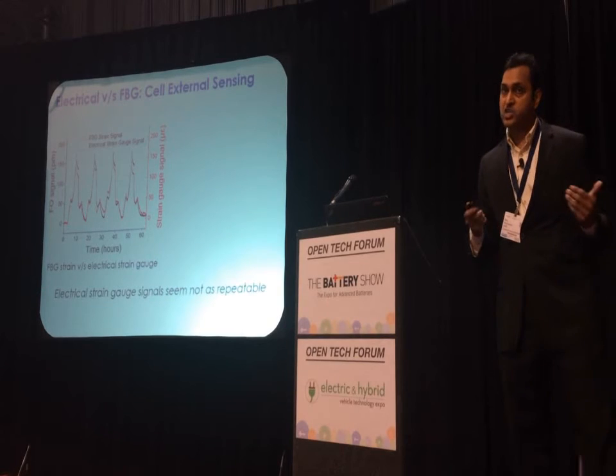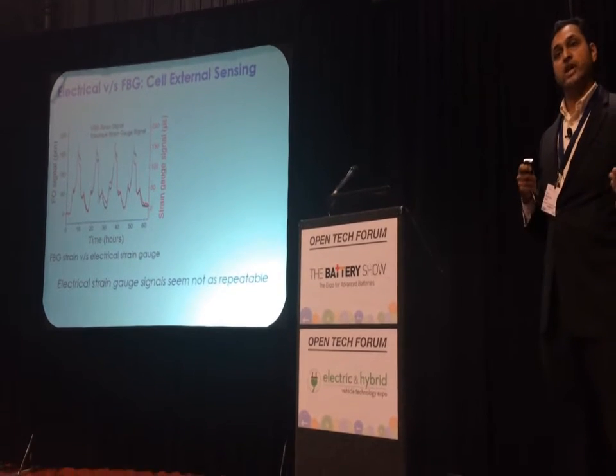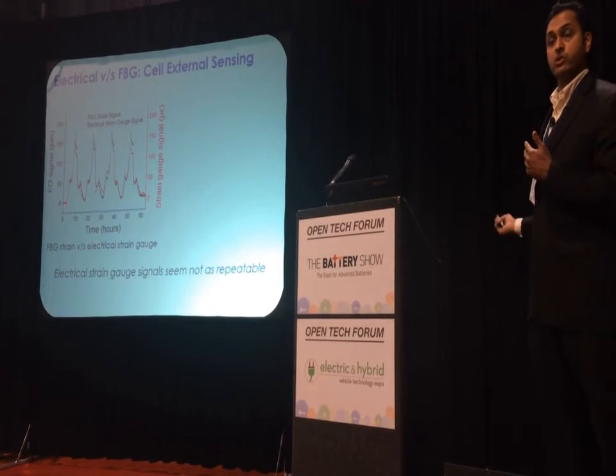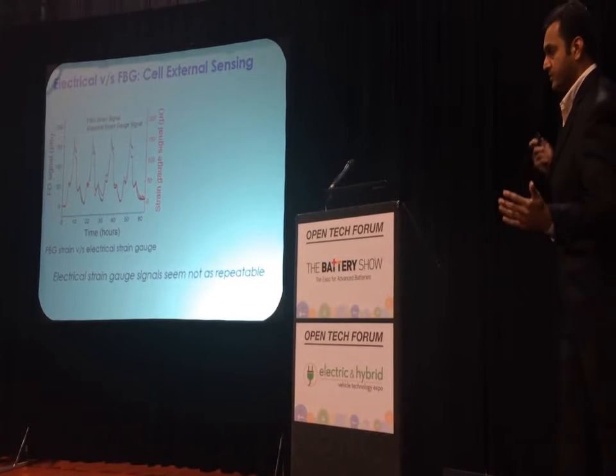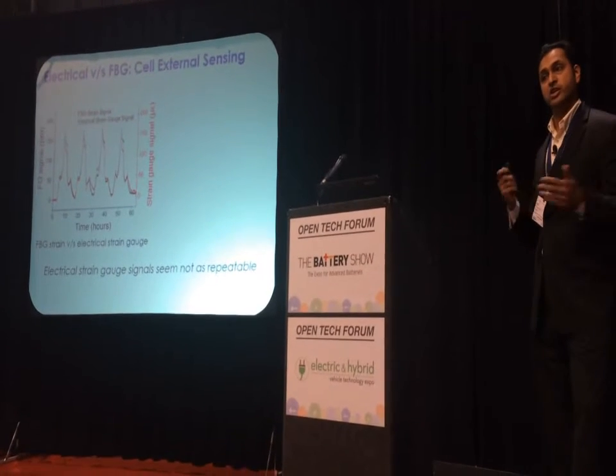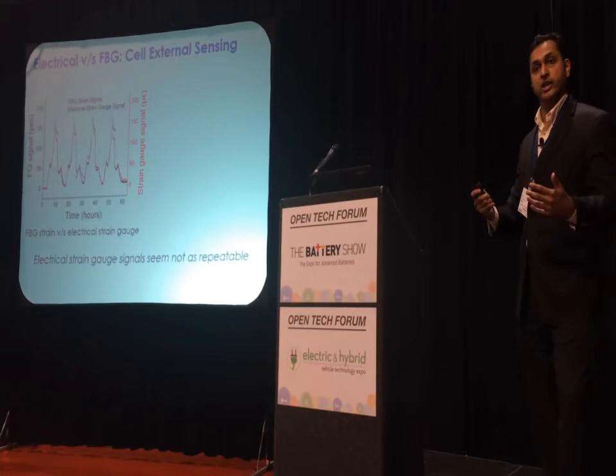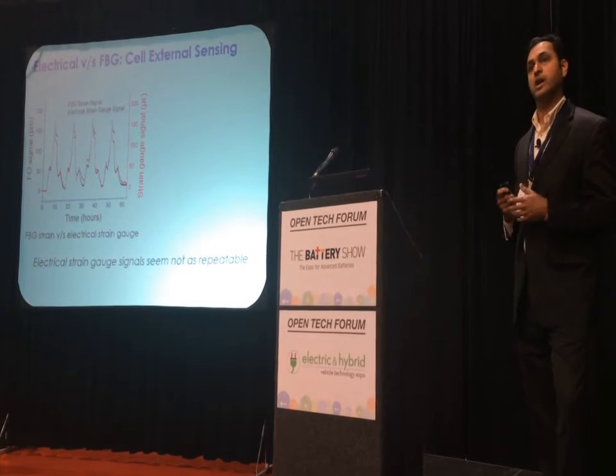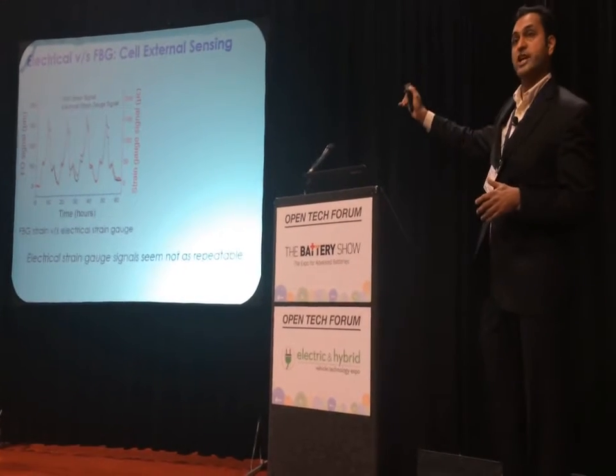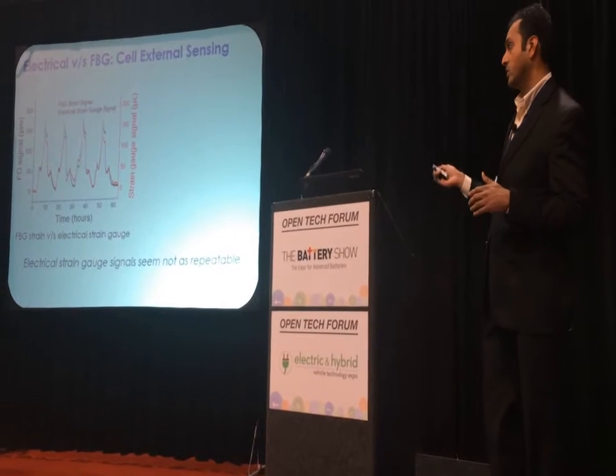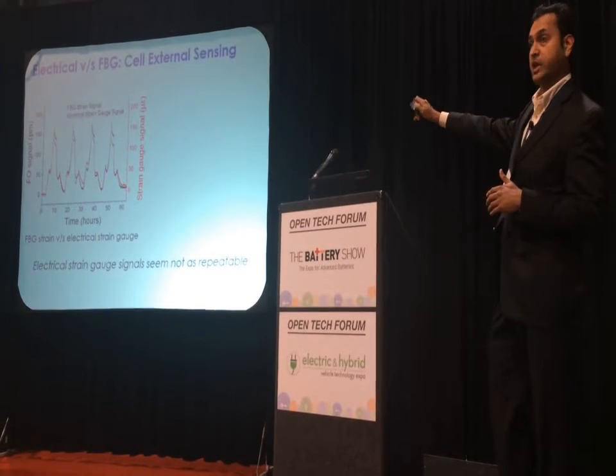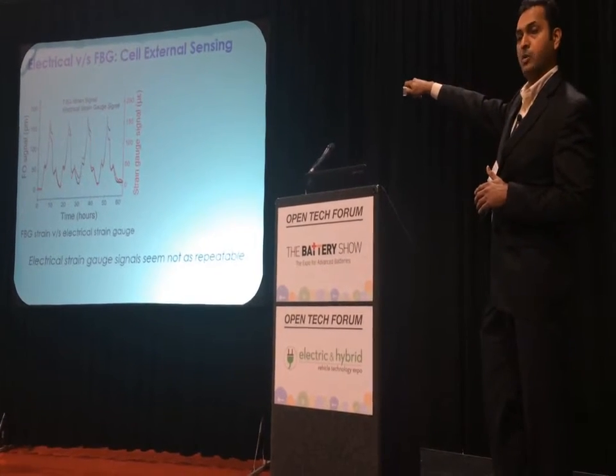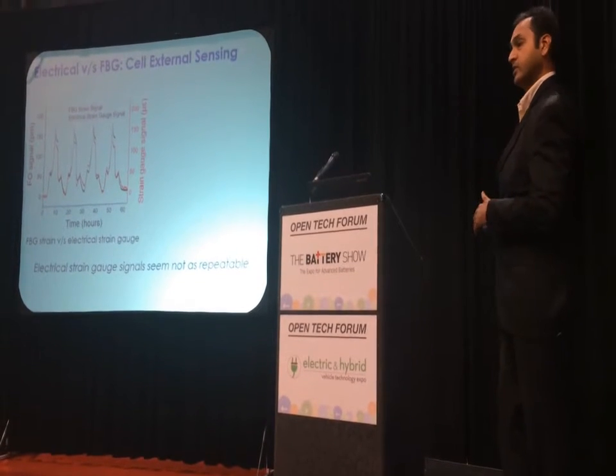For the external sensing use case, one might argue you can do it with electrical sensors. Apart from the disadvantages I already mentioned, like heavier cabling and sensitivity to electromagnetic interference, in our initial tests with electrical foil strain gauges we saw that the strain signal was nowhere near as repeatable as the fiber optic strain signal, which is plotted in black here.